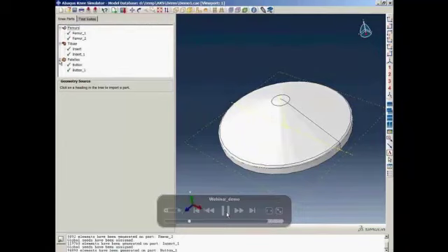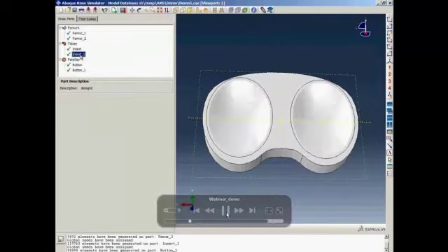Once the implant parts have been imported successfully, they will have a green check mark next to them in the knee part tree. The user can choose to edit the surface and landmark points if they happen to pick the wrong surface or the wrong points. They can also swap the dwell points if they mistakenly enter the lateral side for the medial side. They can do it here.